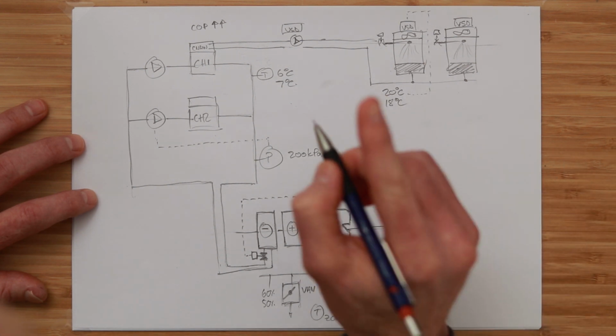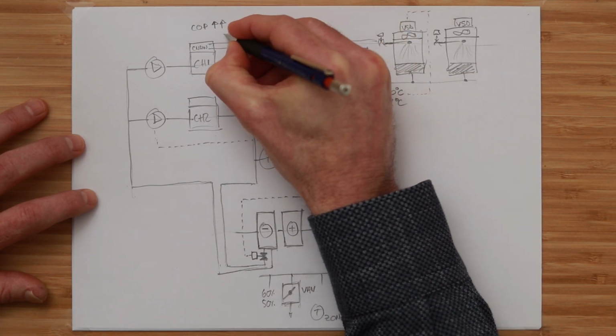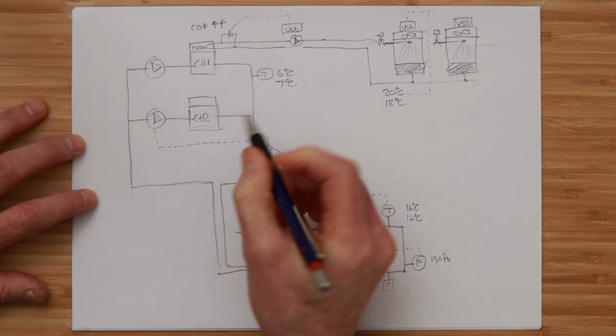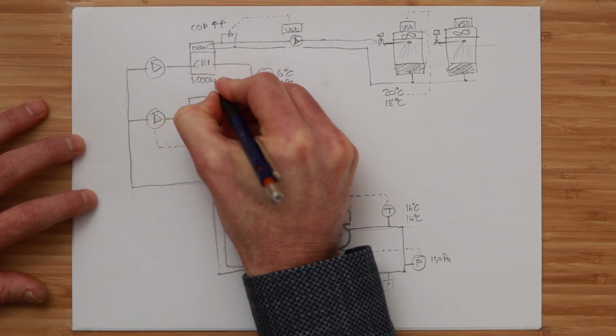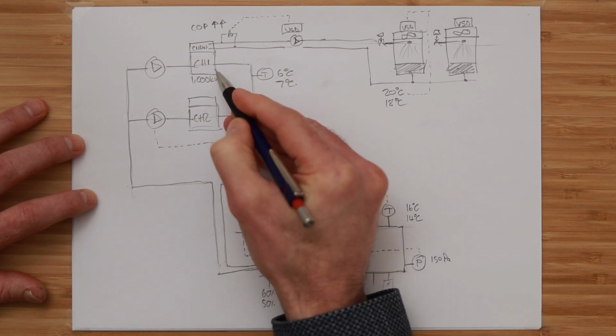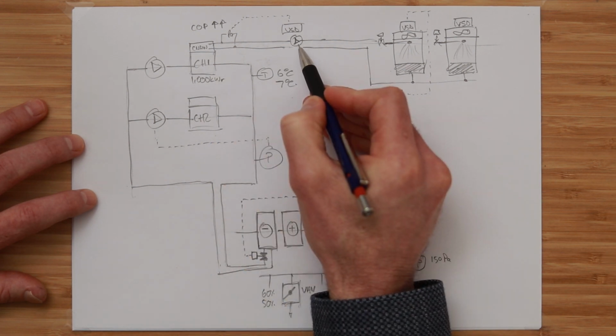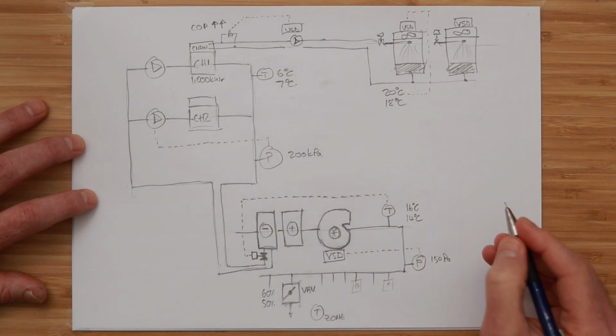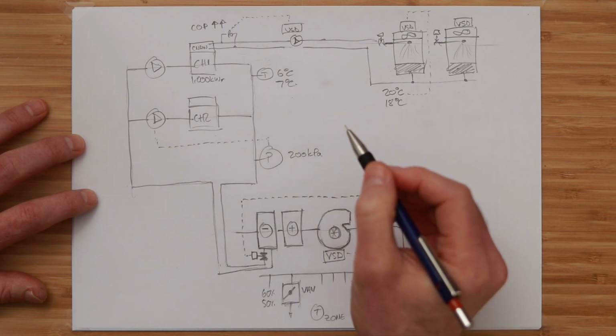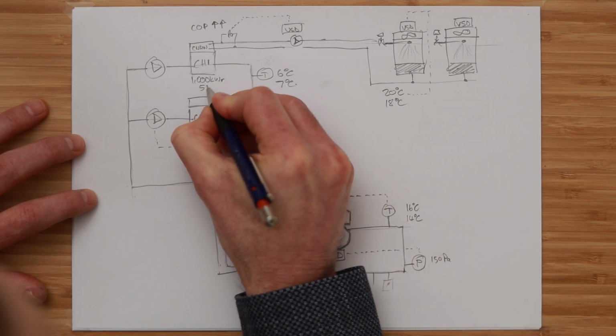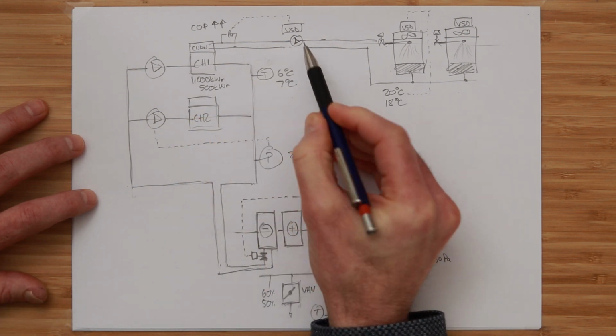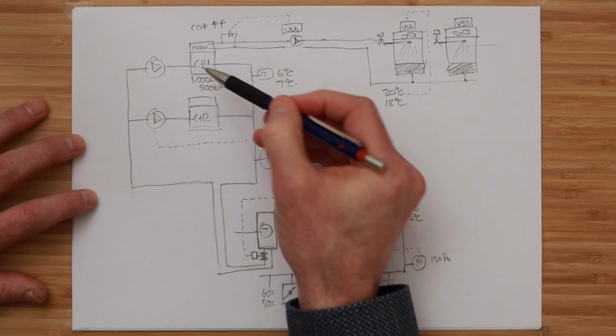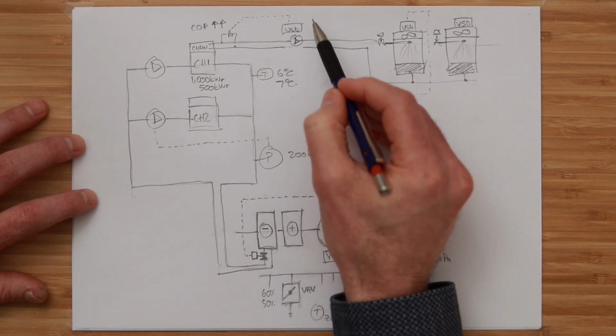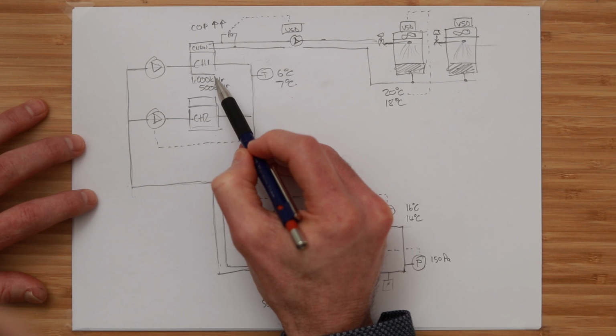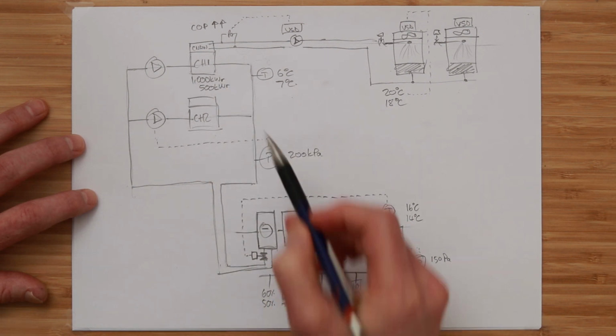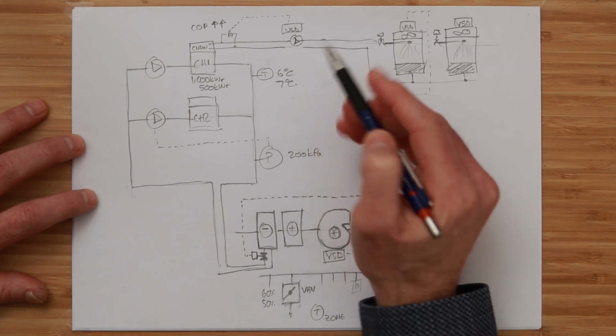What we sometimes do, not very often, is this: if the chiller is running at full capacity, say it's running at 1000 kilowatts of refrigeration, at full design capacity, we've got to run the pump at full design volume to reject all the heat for the chiller to work properly. But if the chiller is running at, say, 50% capacity, we probably don't really need to run this pump at full design volume because the chiller is not running flat out. So occasionally we have an optimized control strategy where as the chiller's capacity is reducing, there's less load out here. We slow this pump down just a tiny bit, not a lot.